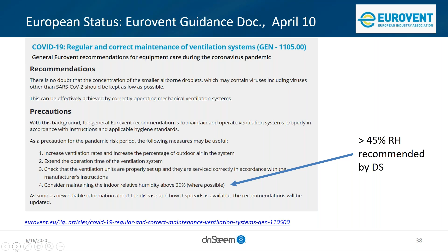The suggestions made after the H1N1 pandemic to the CDC, and then ASHRAE and ASHE's CIAQ document mentioned earlier, are likely relevant to COVID, mainly a holistic approach to mitigation of the virus in a phased or stepped approach, where increased humidity levels form the backbone of a strategy that includes increased air changes, effective UV either in-duct or in-room, improved bathroom exhaust, and finally effective filtration greater than MERV 13.